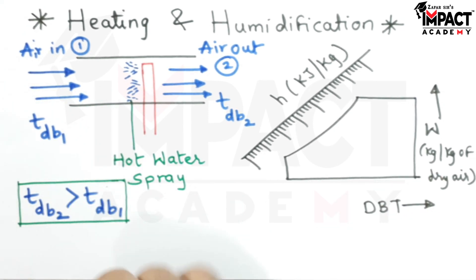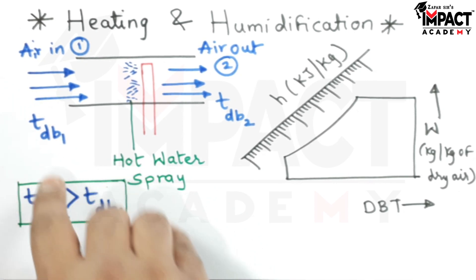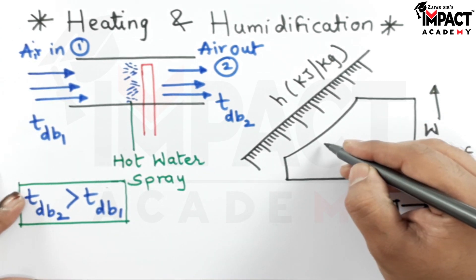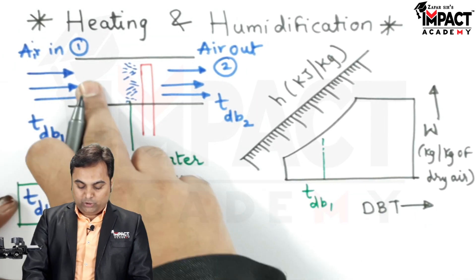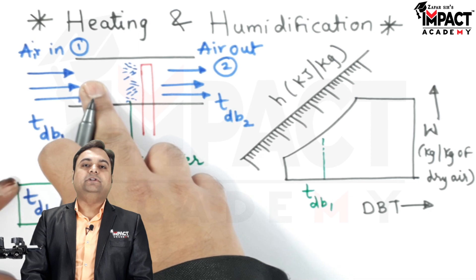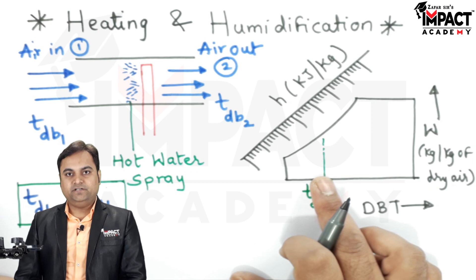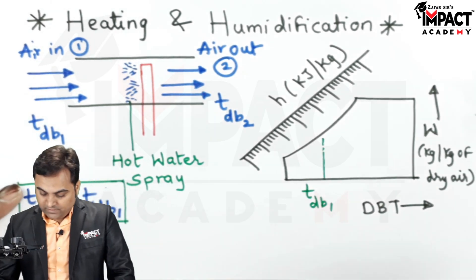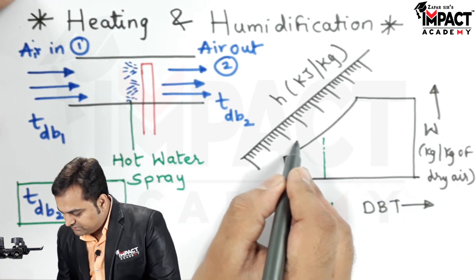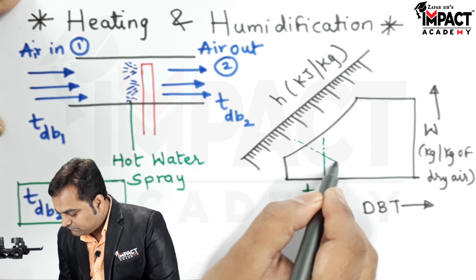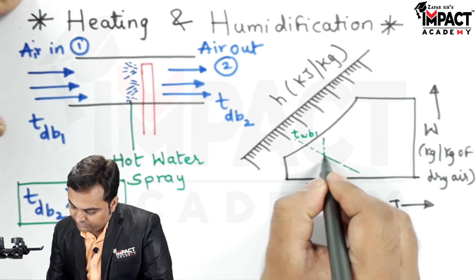To plot the given process, the incoming air is at a considerably lower dry bulb temperature tdb1. To locate point number 1 on the chart, we need at least two properties of the air at the inlet. I'm assuming we have the wet bulb temperature twb1 for the incoming air, and the intersection of tdb1 and twb1 gives us point number 1.